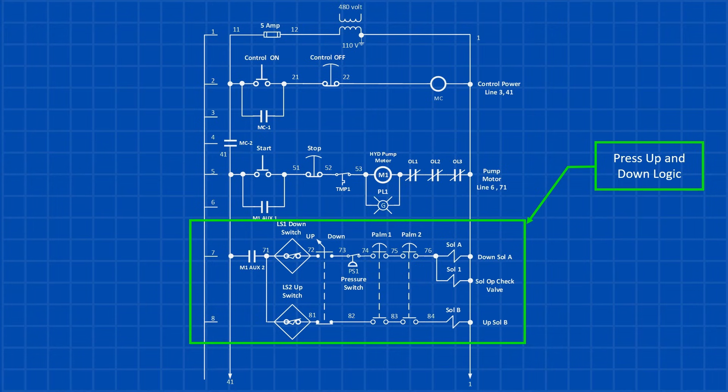If all these conditions are met, when the operator presses the two-handed palm switches, both the check valve and down valve solenoids will energize, causing the press to move down. The press will stop when either the down proximity switch or the high pressure limit switch is activated, which opens the circuit.